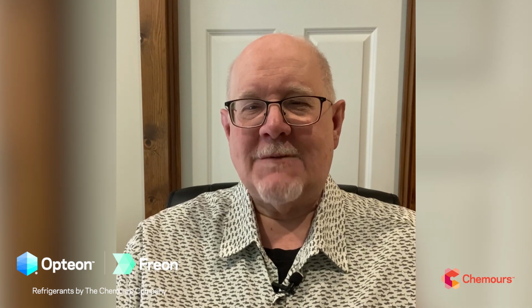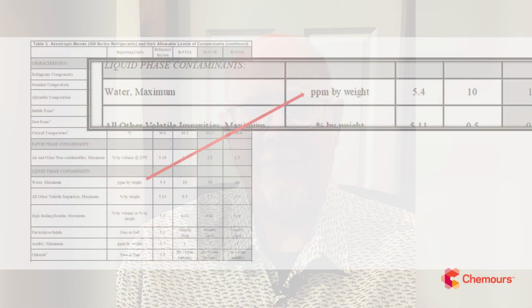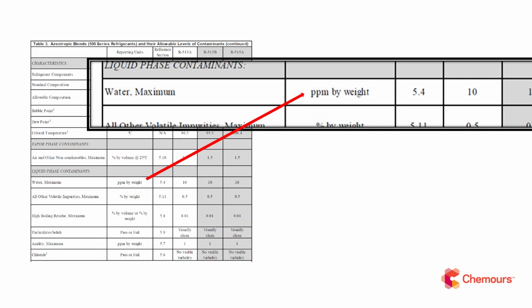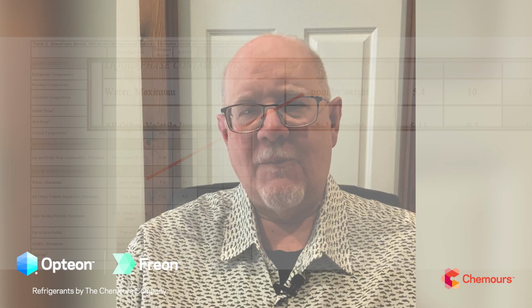So why is this important in the refrigerants industry? Why is it important to people doing refrigeration, HVACR work? A couple places we see it. One, in terms of specifying purity of refrigerants. The AHRI 700 spec has a list of impurities and maximum levels. A lot of those are given in parts per million. For example, 10 parts per million is the maximum allowable quantity of moisture or water in typical refrigerants. So that's not a lot of water.